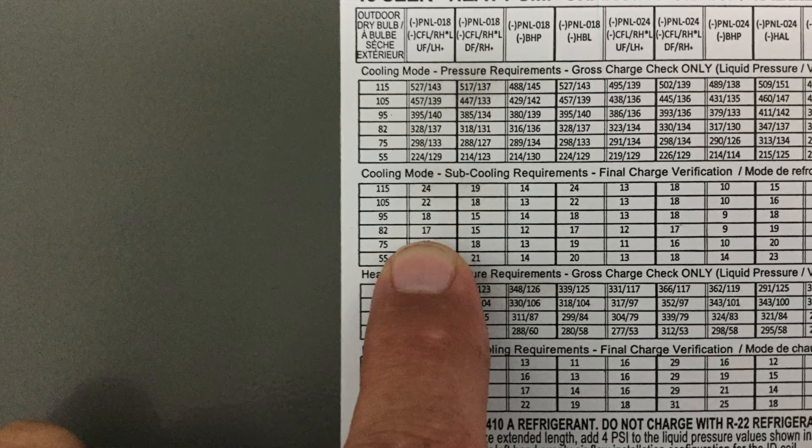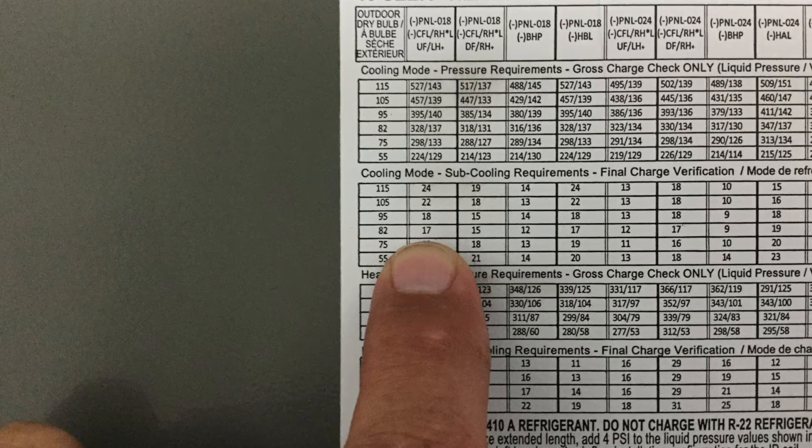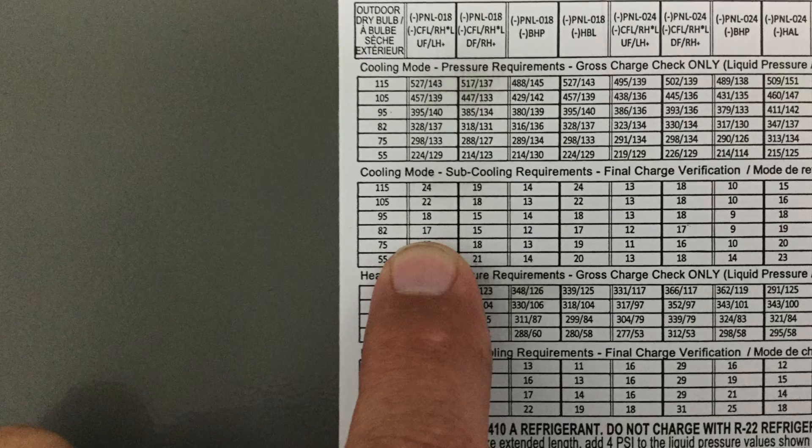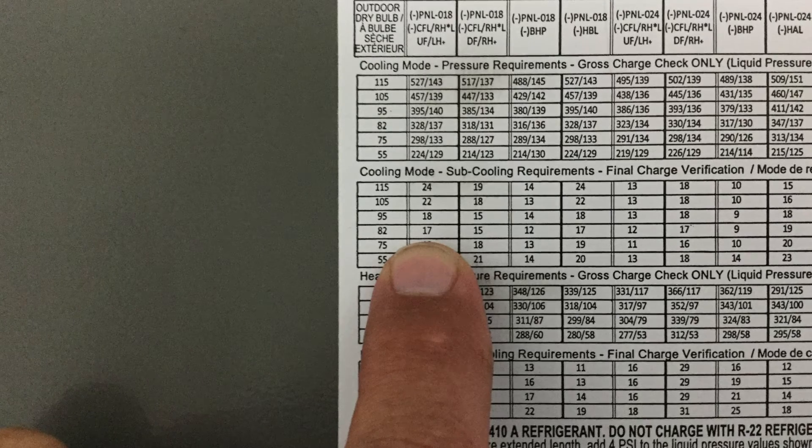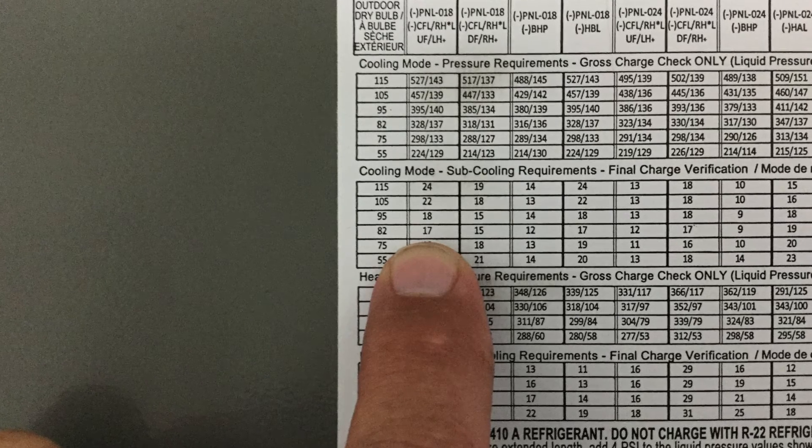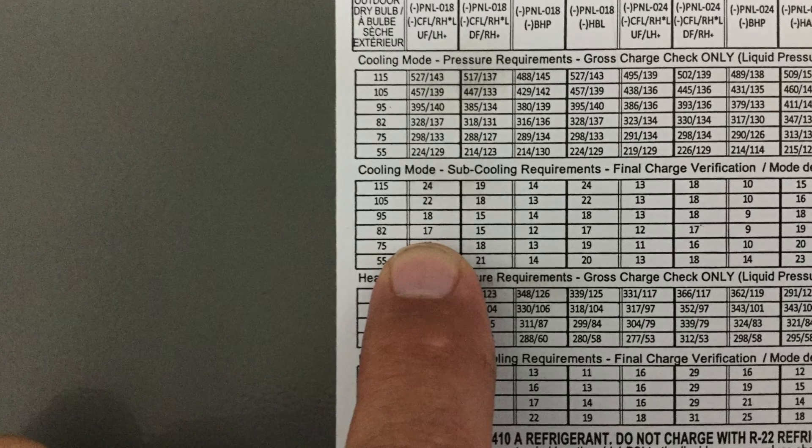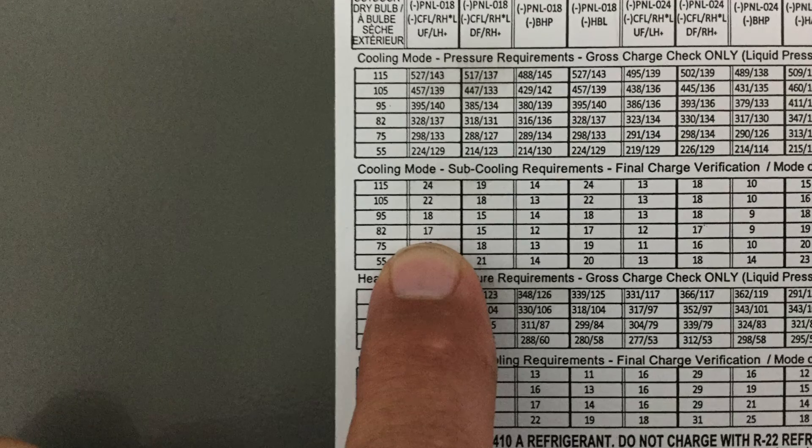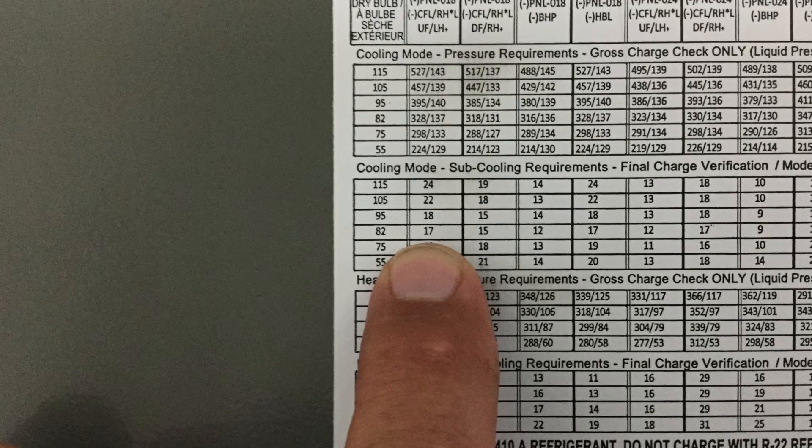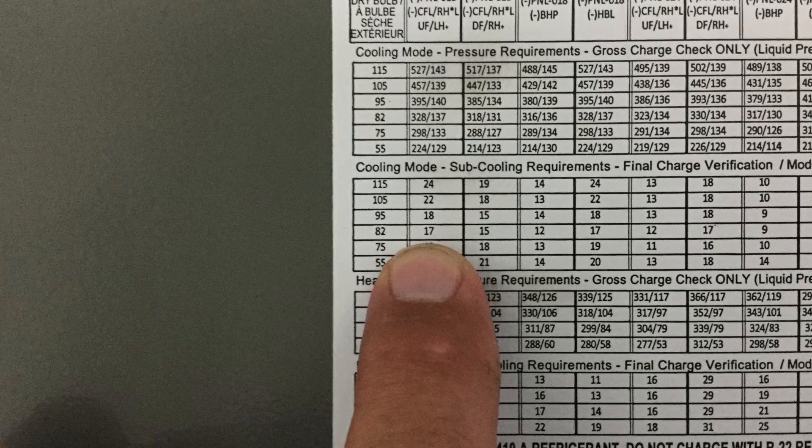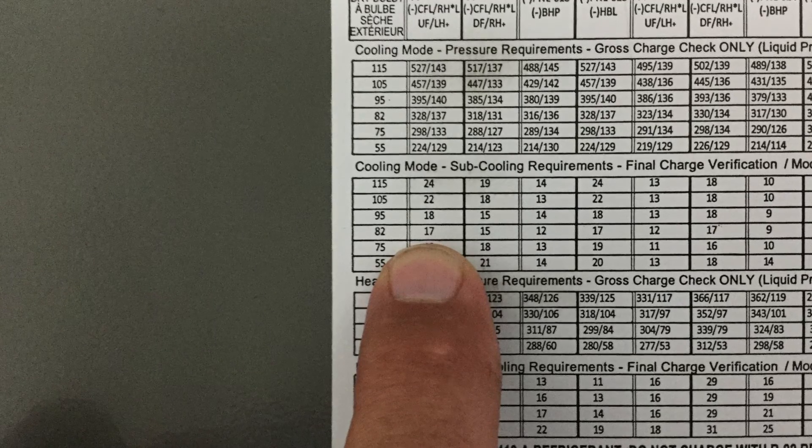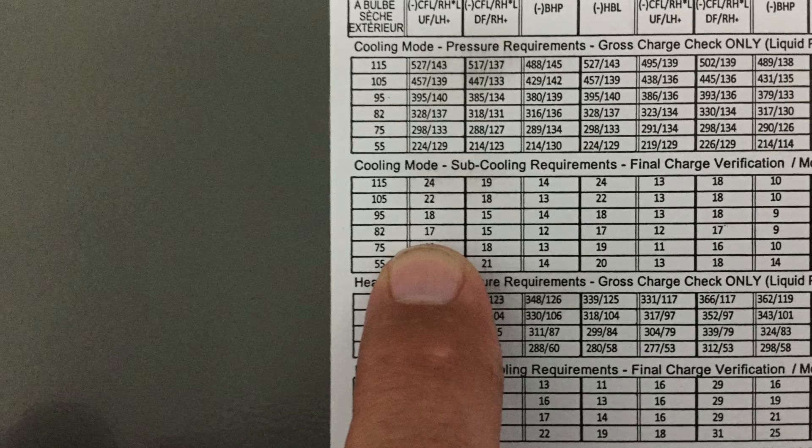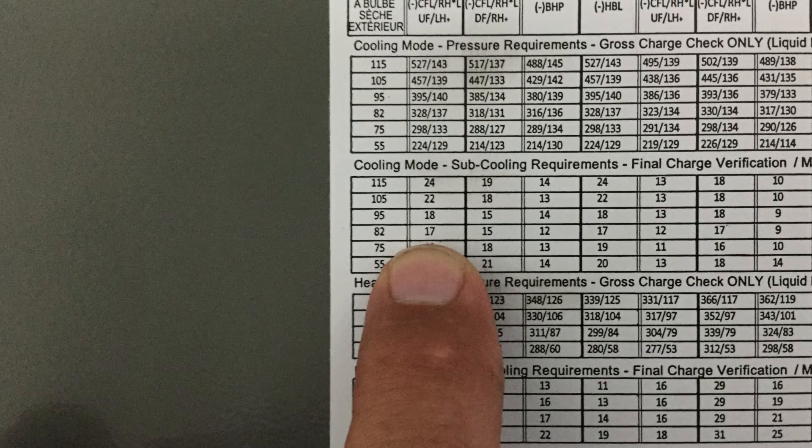Looking here at the chart, you can see that based upon the air handler we have, the PNL-018, and the temperature in the shop being about 82 degrees, our target subcooling is about 17 degrees. So we're going to go ahead and input that in as part of the profile.